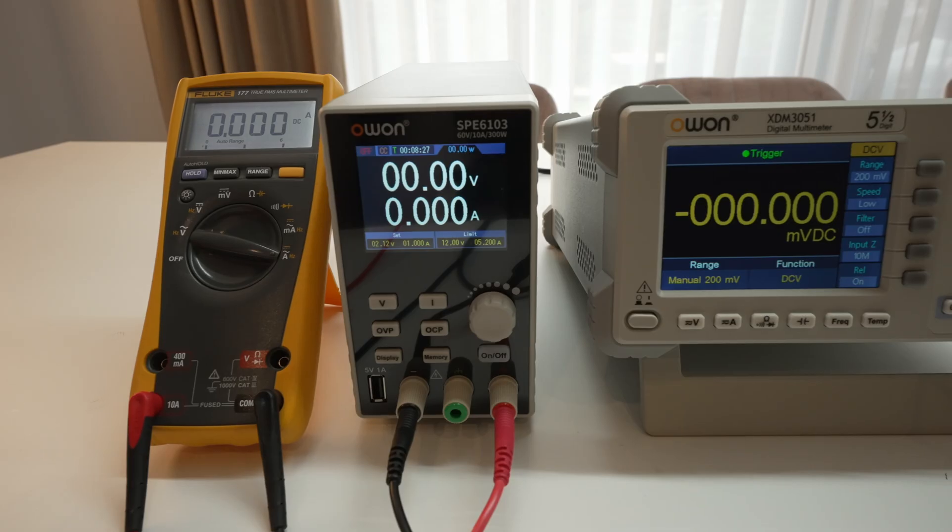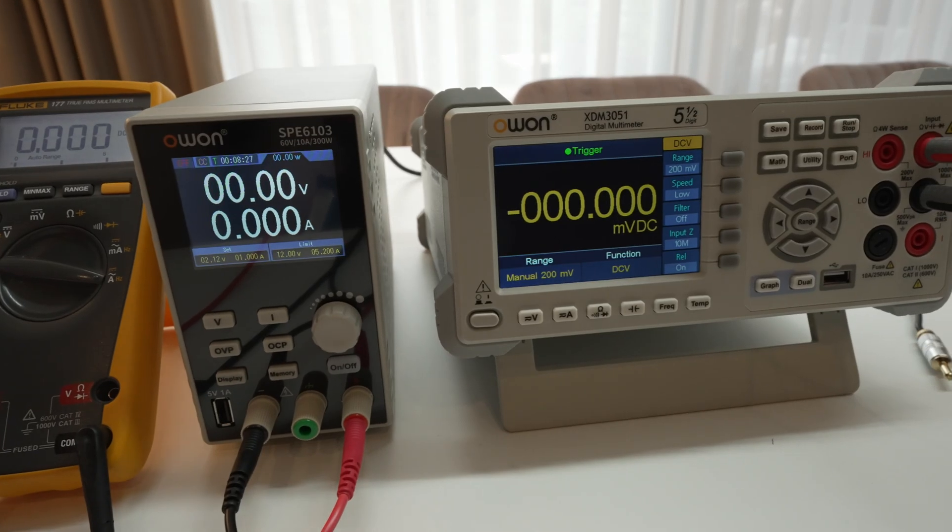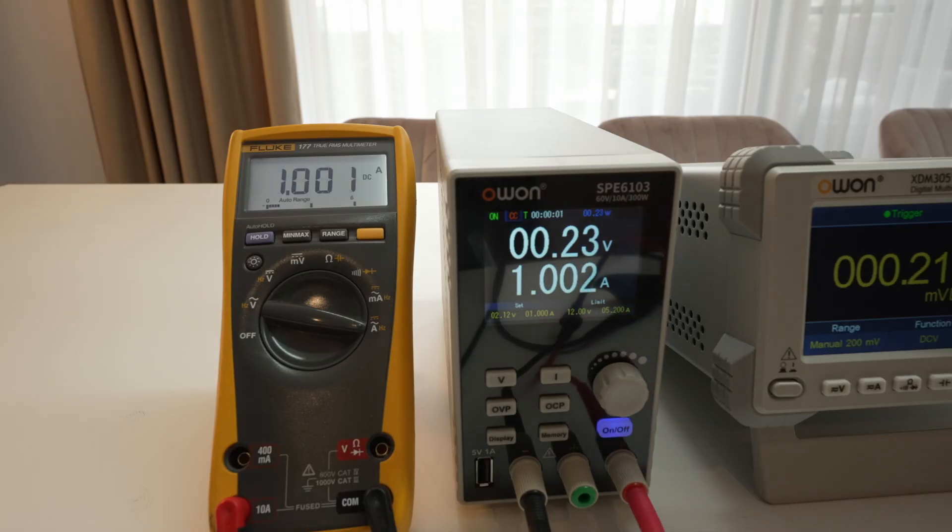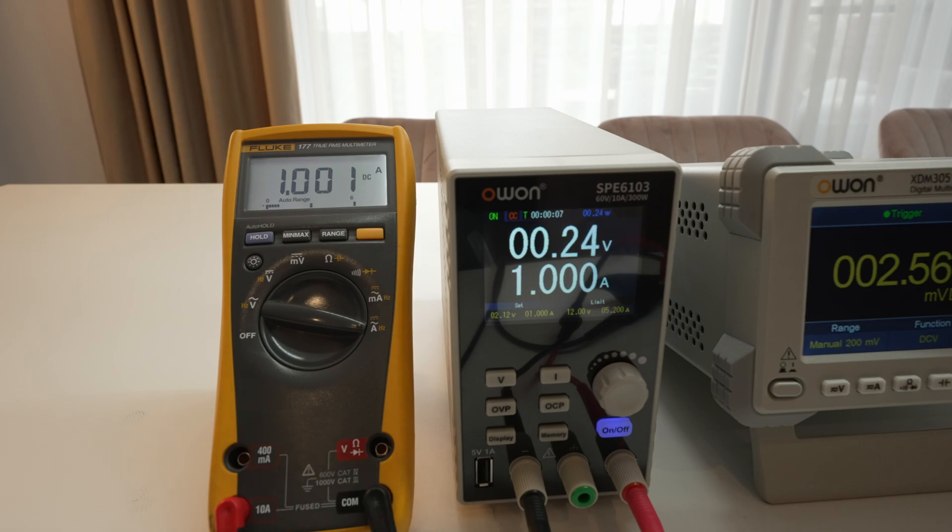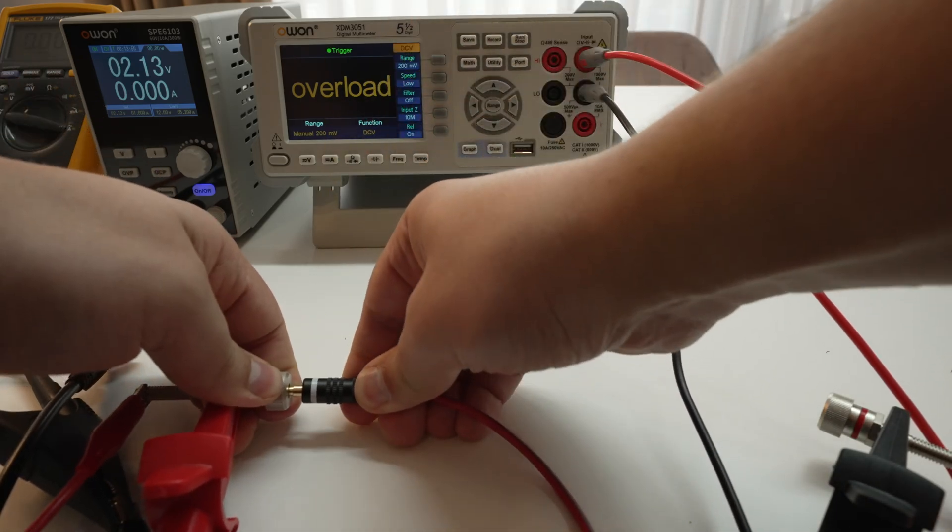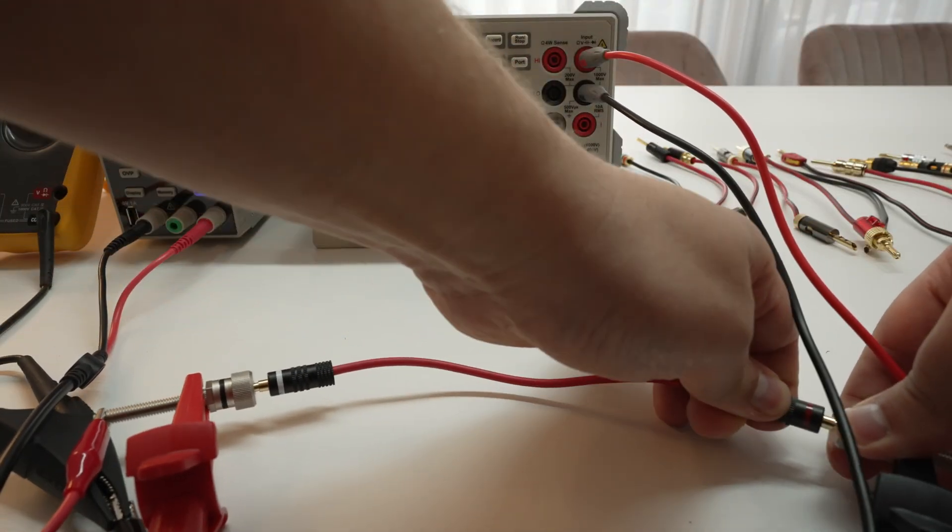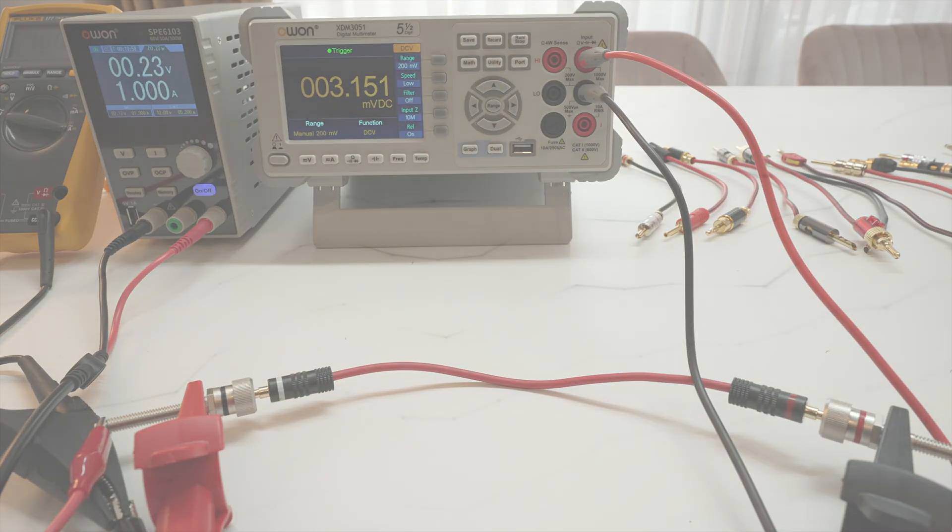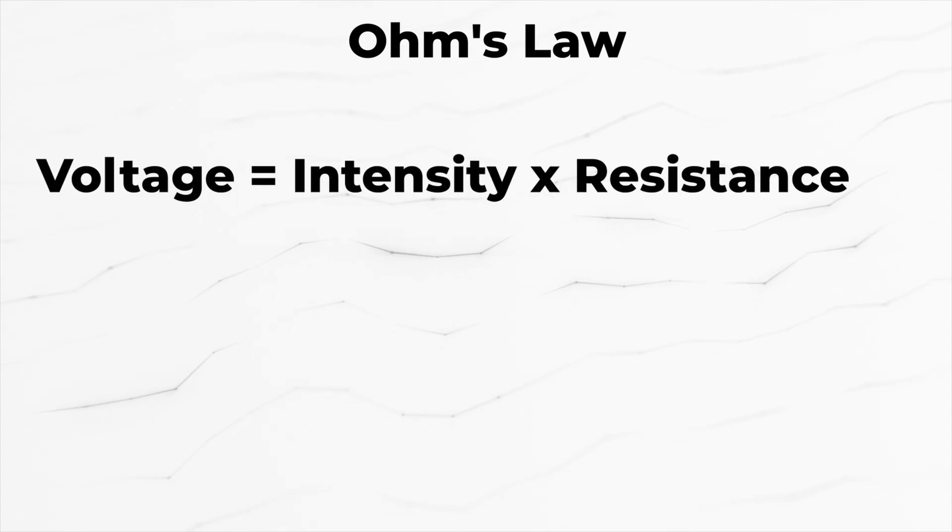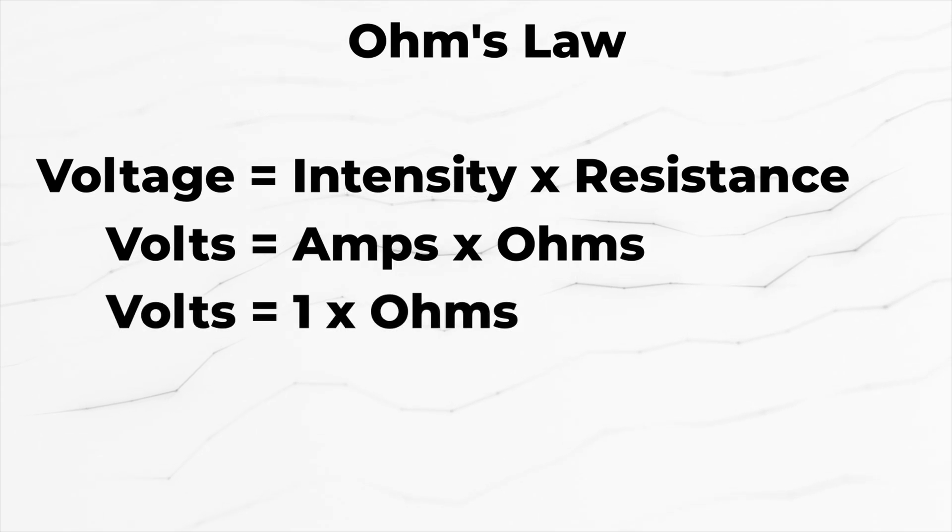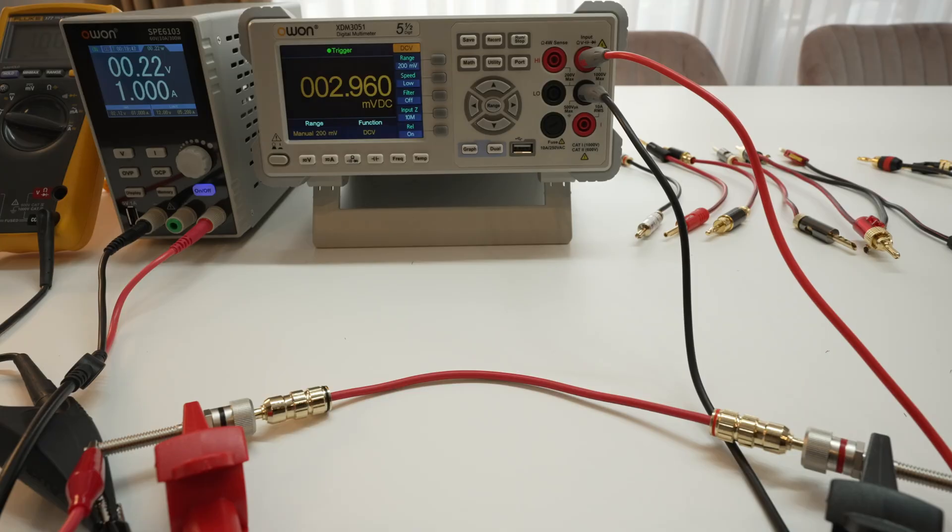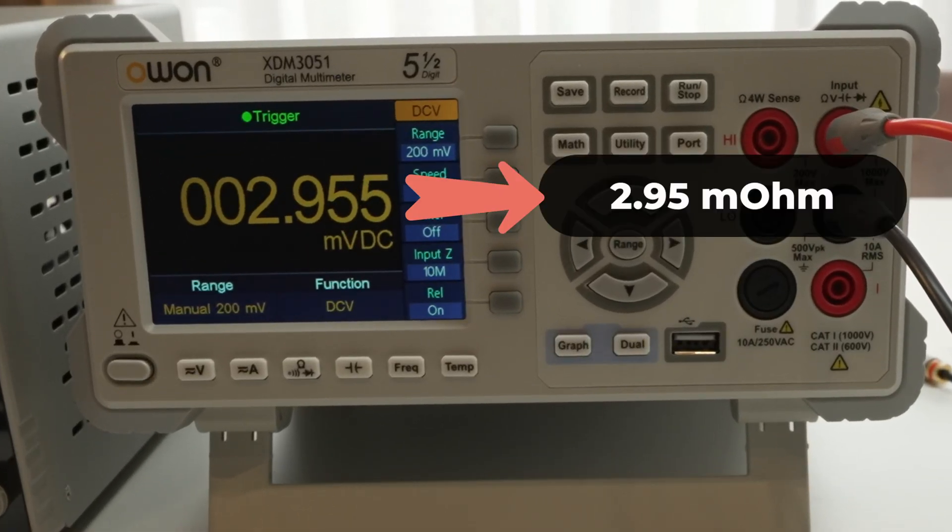Do we have a solution? Yes we do. We bring on more equipment and leverage Ohm's law. I have this power supply which will provide a constant 1 amp of current. This additional multimeter is to confirm that the power supply is not lying to me because I don't trust these. And with the high precision multimeter we'll measure the voltage across the binding posts which this time has an accuracy error way beyond our scope of the measurement. Since Ohm's law is voltage equals to intensity times resistance, which is basically volts equals to amps times ohms, we have 1 amp on the circuit, so basically volts equals to ohms. As a result, whatever reading of millivolts we get, that is basically the equivalent in milliohms.